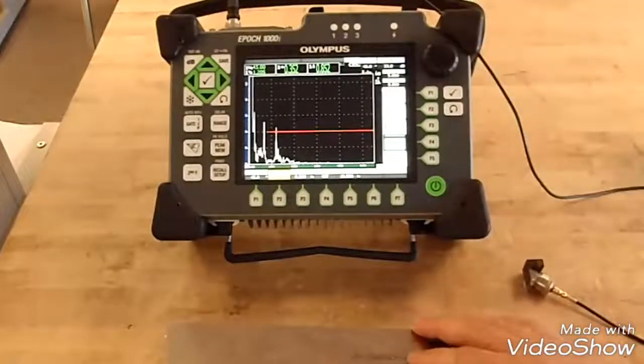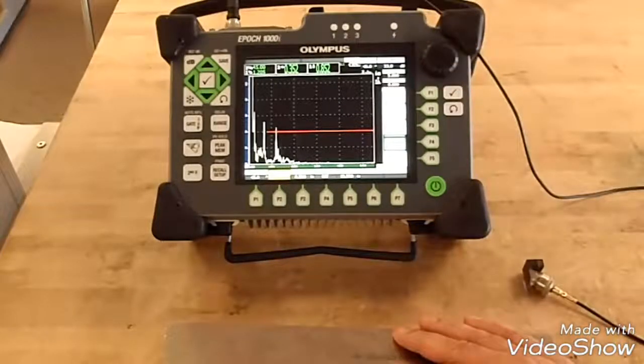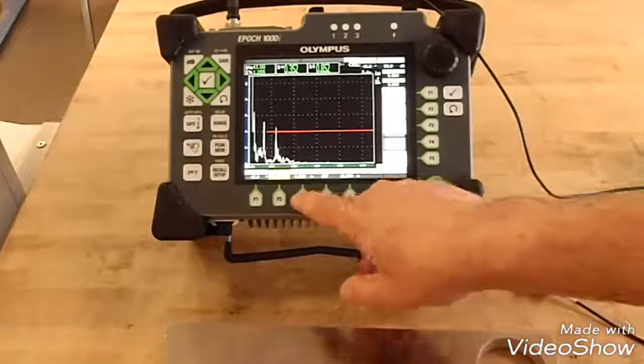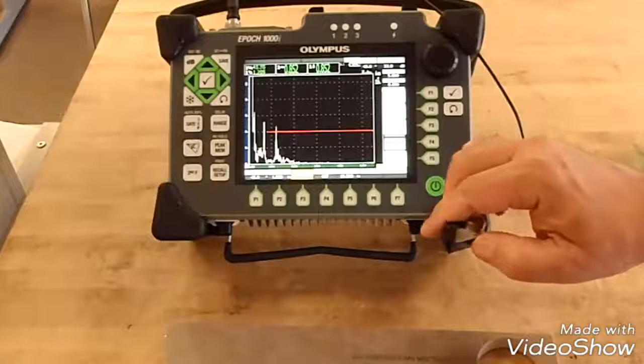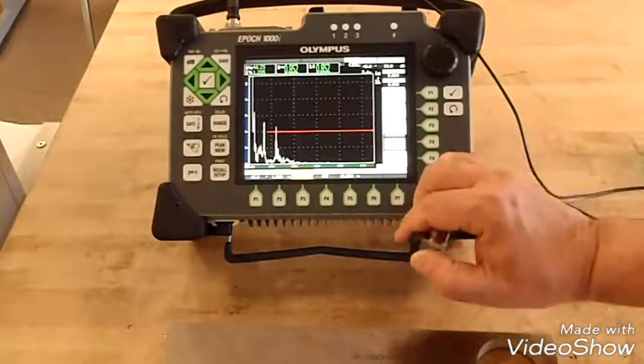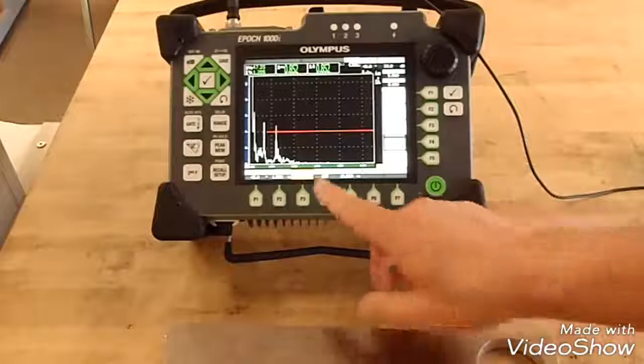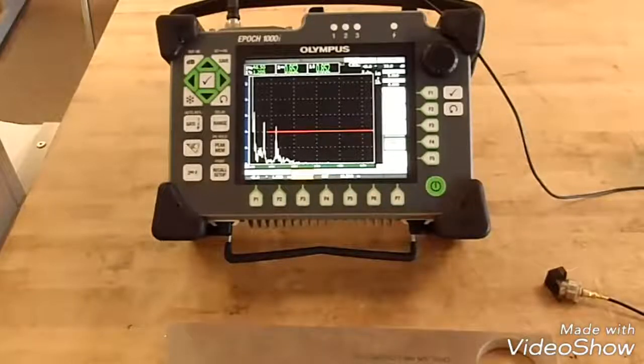The X value I'm gonna leave at zero. That X value is the measurement from the front of the wedge to the beam index point. Curved surface correction turned off.